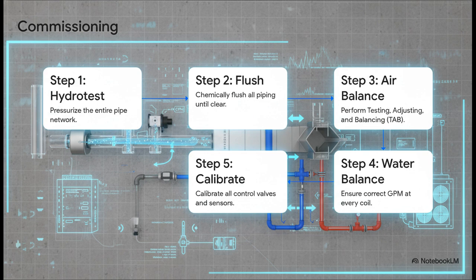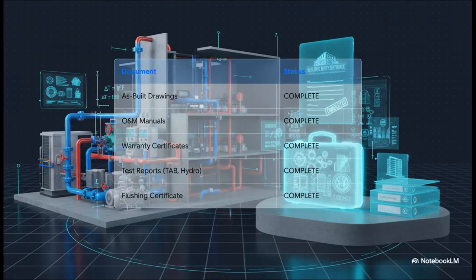First, that hydro test. Then we do a full chemical flush to get rid of any grime or metal shavings left over from construction. Then, in steps 3 and 4, a team of specialists comes in to do what's called TAB, testing, adjusting, and balancing. They fine-tune the system so that every single room gets the exact amount of air and water it was designed for. And finally, every last sensor and valve is calibrated so it reports accurate data to the building's central computer brain, the BMS. A project is only officially done when this package is handed over. And this is way more than just a stack of paper. It's the building's official birth certificate. It has the final as-built drawings, the owner's manuals for every single piece of equipment, and most importantly, the signed test reports that serve as cold, hard proof that the system is performing exactly as promised.